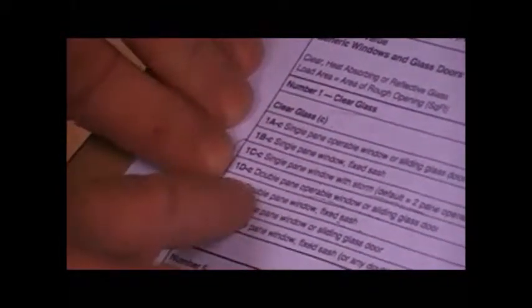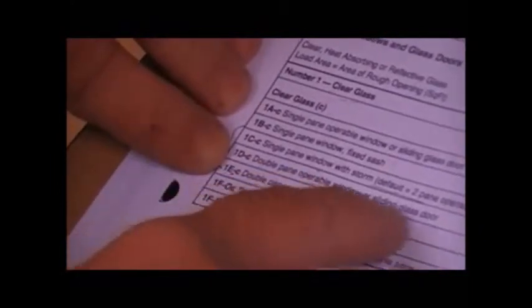Now, our windows, and I'm hoping I'm not losing you here, it gives us our dimensions on our example and identifies the windows with A and B. But our description of the windows says all windows are double pane clear glass operable sash with a wood frame. That's a lot of information, I know, but we got to go through there. If we look through our Table 2, we find that we have clear glass under this heading here, double pane operable window or sliding glass door. Well, we're not dealing with a sliding glass door, but we are dealing with the double pane operable window.